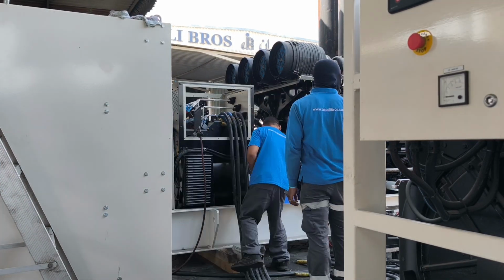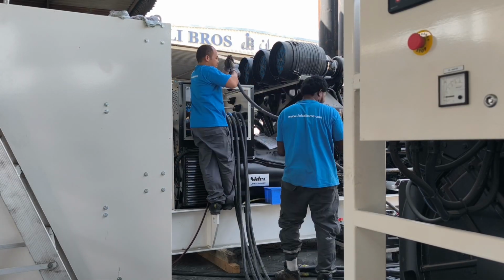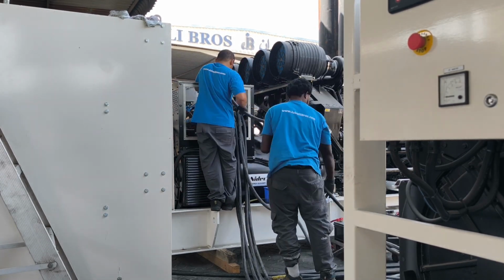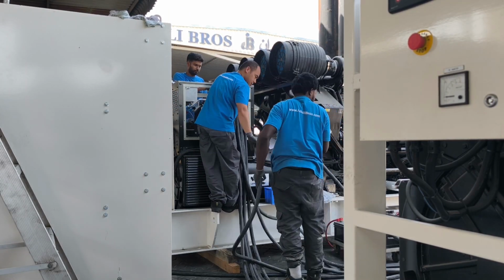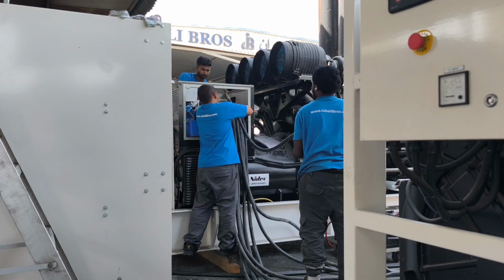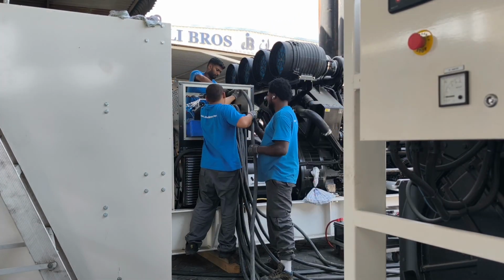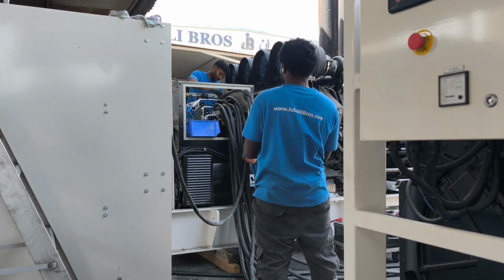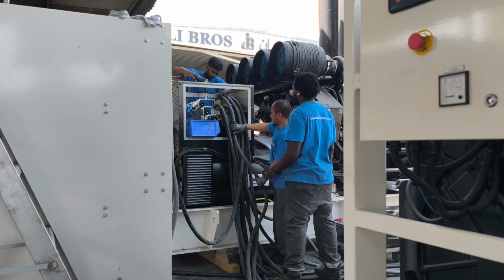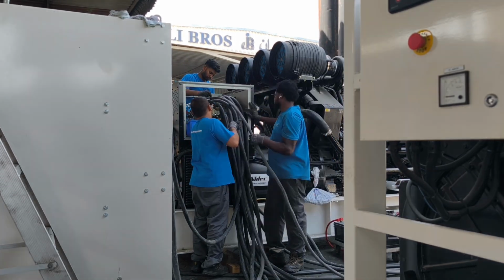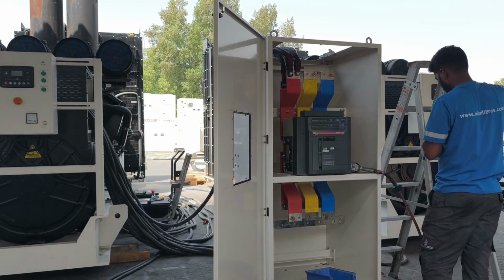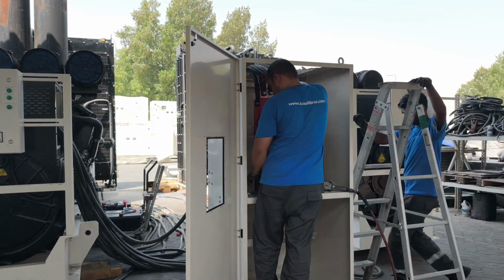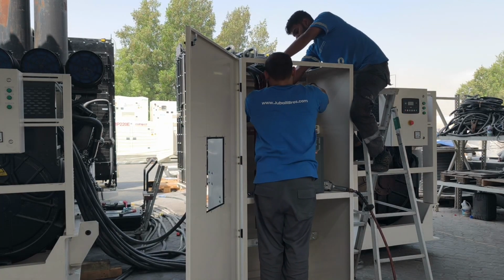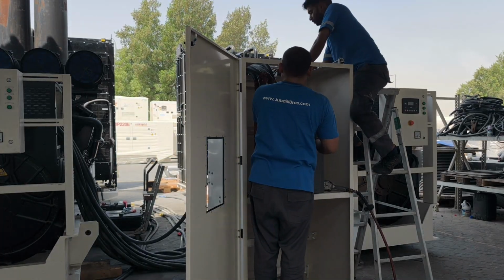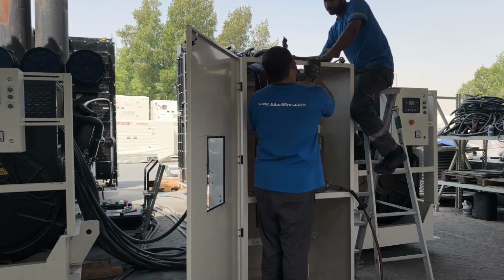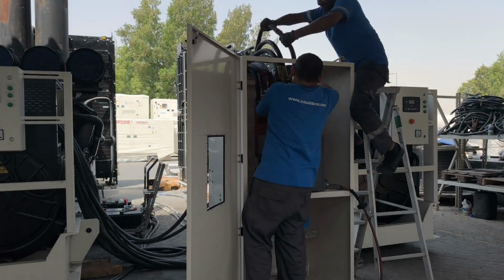So this is how we prepare for our power cabling for our 2000 kVA generator, and we have a lot of cable that we are going to install so we can do our load testing. Just watch until the end so we can see how we will make it during the tests and what will happen. By the way, this is 2 pieces of 2000 kVA that we're going to do the load testing on. So we need to check everything: the vibration, the power capacity, the temperature, the oil pressure, all the things that are necessary. We're going to check until we succeed in our testing.